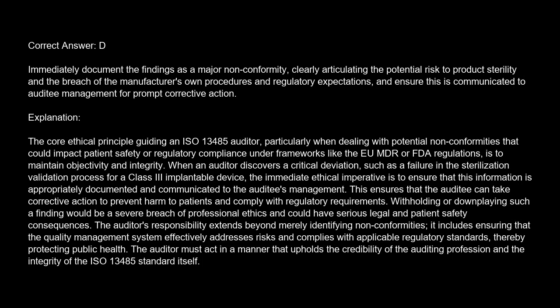Correct answer is D. Immediately document the findings as a major nonconformity, clearly articulating the potential risk to product sterility and the breach of the manufacturer's own procedures and regulatory expectations, and ensure this is communicated to auditee management for prompt corrective action. Explanation. The core ethical principle guiding an ISO 13485 auditor, particularly when dealing with potential nonconformities that could impact patient safety or regulatory compliance under frameworks like the EU MDR or FDA regulations, is to maintain objectivity and integrity.